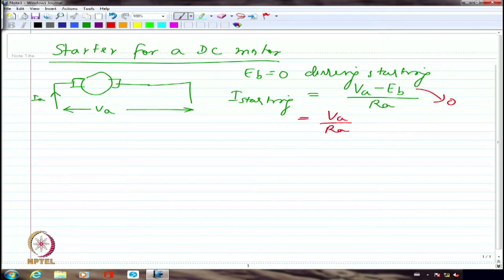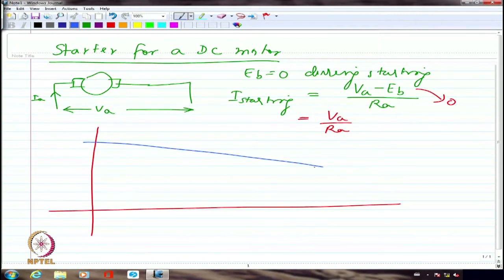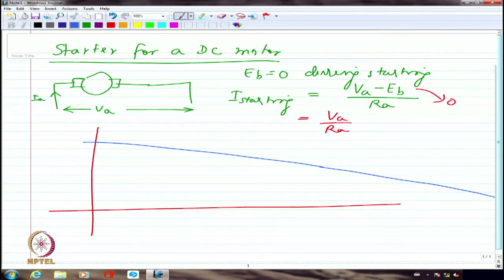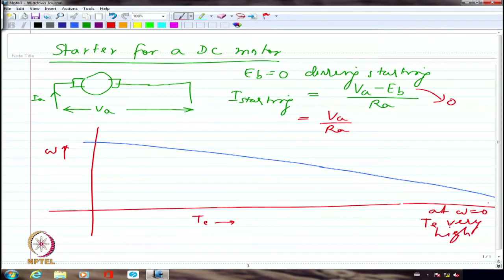This starting current is going to be extremely large. As we indicated in the last class from the speed-torque characteristics, if we extend the characteristic until it intersects the torque axis, the electromagnetic torque developed at speed equal to zero is going to be enormously high — far beyond the board. So the torque will be very high if we do not include any external resistance.